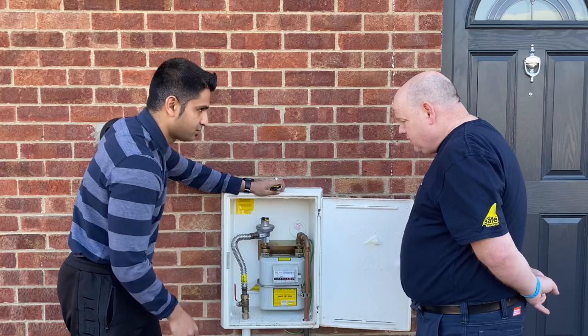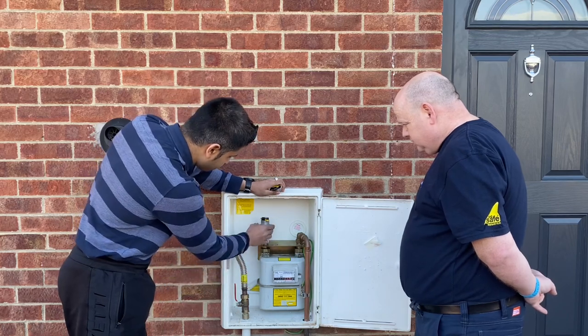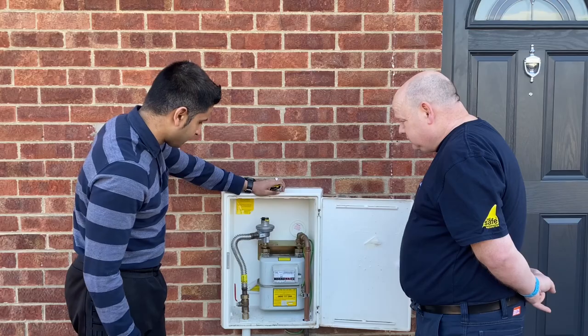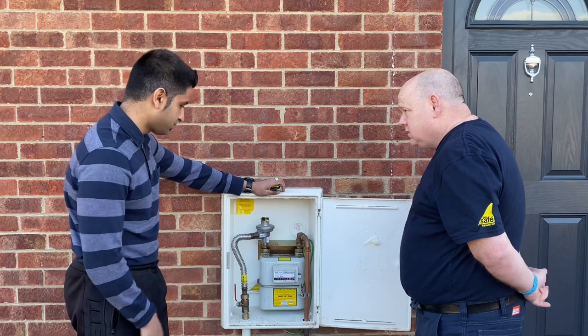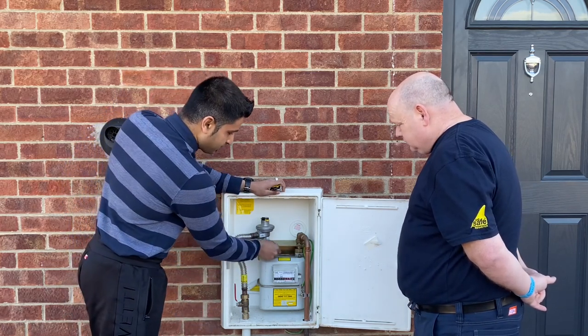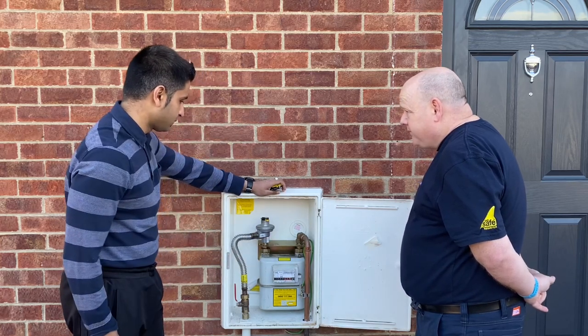Going off the governor, you need to make sure that the seal is on the governor — that's just to make sure that it's not being tampered with. On the meter itself you should have the emergency number; this is the number for Cadent, so if you smell gas or anything like that, that's the number that the customer needs to be ringing. You also need to be making sure that the meter itself is secured and that it looks in good working condition.